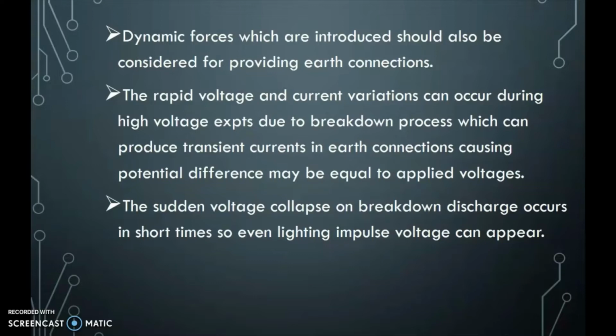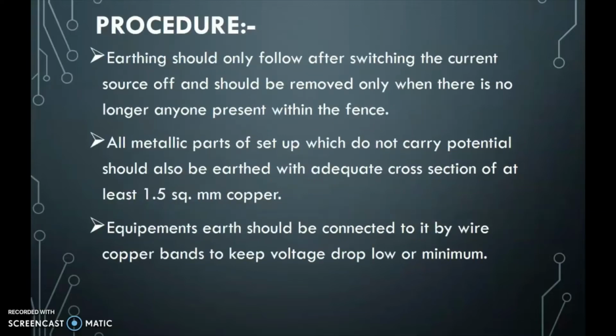Rapid voltage and current variation can occur during high voltage experiments due to the breakdown process, which can produce transient current in earth connections, causing a potential difference that may be equal to the applied voltage. The sudden voltage collapse on breakdown discharge occurs in a short time, so even lightning impulse voltage can appear. All these facts are required to be considered for providing safety measures like earthing and fencing.